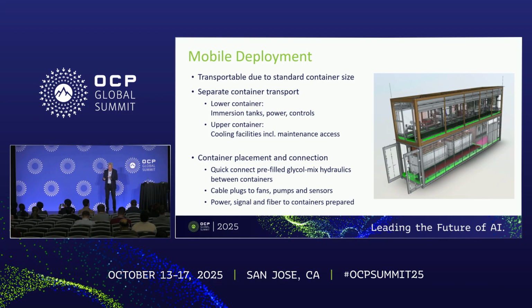In the lower container are the tanks and electrical distribution control, and the upper one is the mechanical equipment. We have two containers put on top of each other. Once the lower one is in place, you put the upper one on top, with a little connection piece of tube. You vent it and connect it hydraulically and electrically. Cables are pluggable, so very rapid - that's the principle for mobile deployment, to be fast.